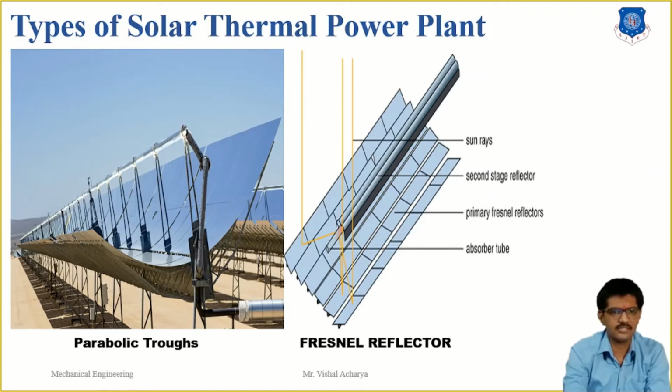Here, linear concentrating solar power collectors capture the sun's energy with large mirrors that reflect and focus sunlight onto a linear receiver tube. The receiver contains a fluid that is heated by the sunlight and then used to heat water in a traditional power cycle that spins the turbine and drives the generator to produce electricity. Alternatively, steam can be generated directly in the solar field, which eliminates the need for costly heat exchangers.